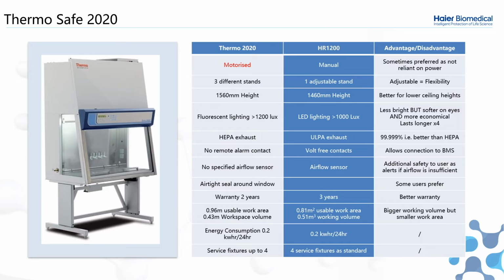Here is the Thermo Safe 2020, a very common model around the world, which we also come across in the UK. They offer a motorised sash as standard, while our standard model comes with a manual sash. One of the main benefits here is that a manual sash is very reliable in the event of a power failure, where it's very easy to close. It's also more reliable as a manual system, as there is no motor to fail, which can happen with a motorised sash.